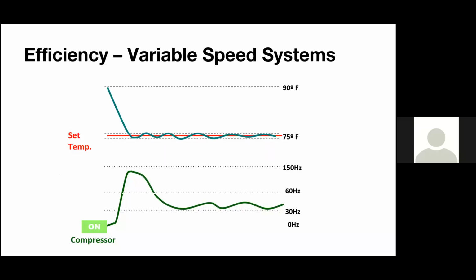So, when you're installing a heat pump system in your home, you might think, okay, it's getting hot in my house, maybe I want to turn on my AC, and then you turn it off 2 hours later. That is not the function of a VRF system. As soon as you're getting away from set point, it's going to take a lot more energy and it's going to work a lot harder to get there. So you want to keep it on. And what's going to happen, looking down at the compressor, is we're going to ramp that compressor way down low, and we're going to only use the energy that's needed.